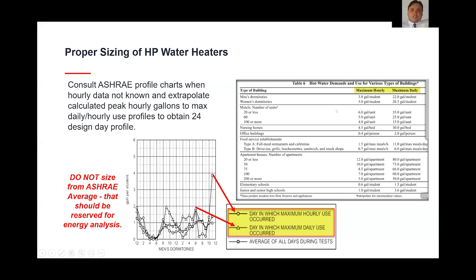And then there's other sources you can use to get a good gut check in terms of where you're at. ASHRAE, again, if you look in, I think it's their application sections, they publish some charts like this that are very conservative because they predate modern low flow fixtures, but they'll give you data like maximum hourly and maximum daily gallon per student in the case of a dorm, or a gallon per person in the case of an office building. It just depends on the building type.